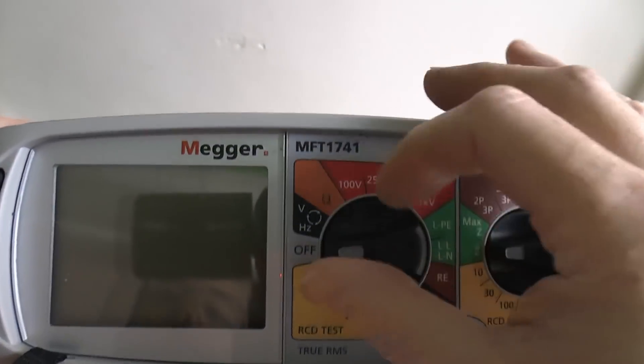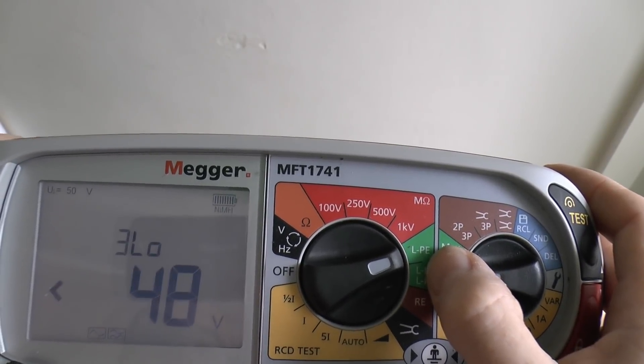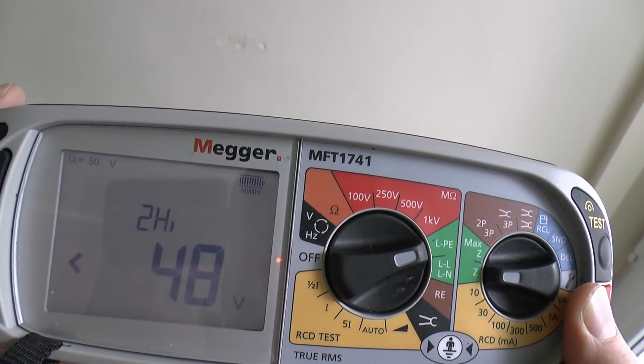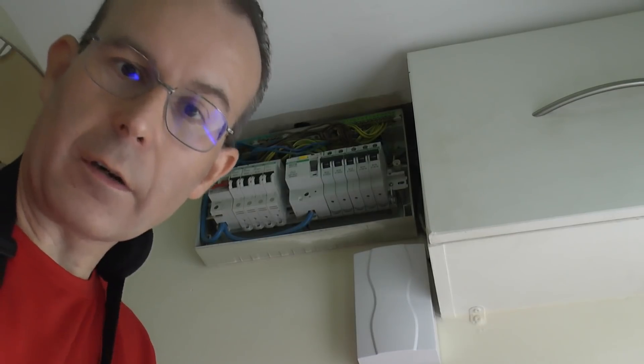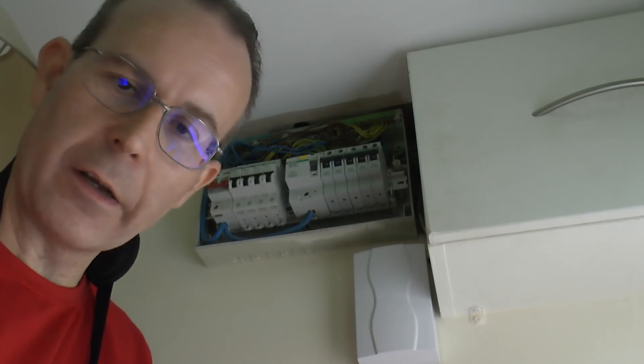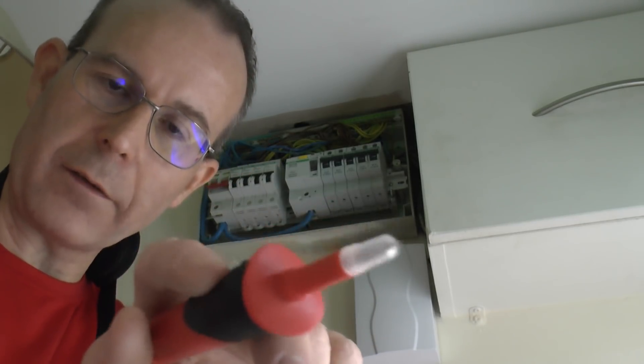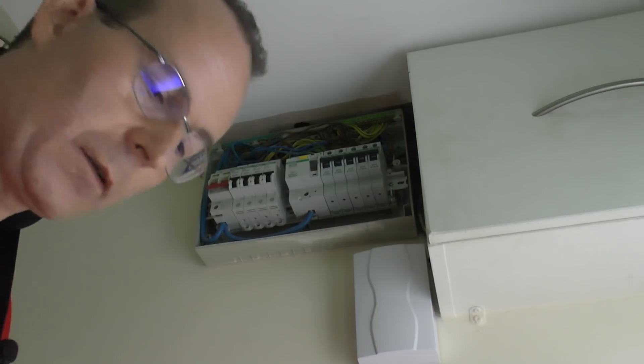Here's the test instrument we're going to use this time — the Megger MFT1741. We want to turn the control to the loop testing function, so just round to LPE there. And we want to be on just Z here — we don't really need the maximum one because we're just doing it once only. Now this is currently on the three-wire low test which we don't particularly want, so we'll change that by the button here to two-wire high current, and then just need to attach our wires and see what result we get.